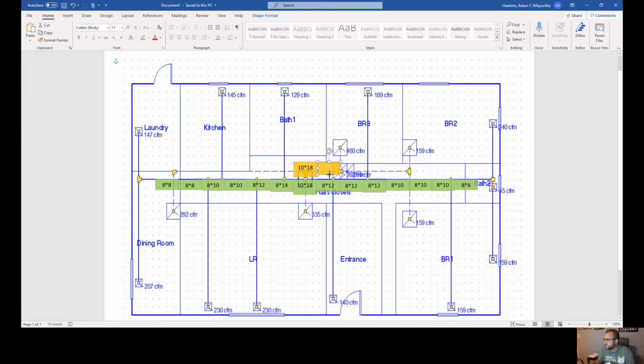So the first piece of duct looks like it's going to be right on the edge, but let's say it catches it. The first piece of duct has to handle 1 bedroom, 2 bedrooms, 3 bedrooms. That's your 3. So if they're 100 apiece, ignore these CFMs, that's 300 on that end.